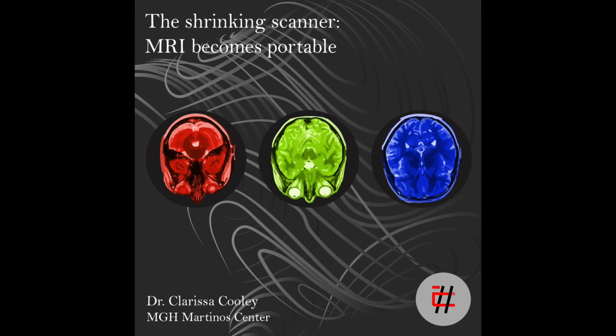The images that I showed in the paper were acquired inside of a shielded room that reduced electromagnetic interference in the images. This is important because electromagnetic interference can be picked up by the receive coils in the magnet, and that results in lower image quality. So to start with, we acquired our images within a shielded room that reduces this, but we're currently working really hard on another method that uses external probes to measure the interference and retrospectively remove it.